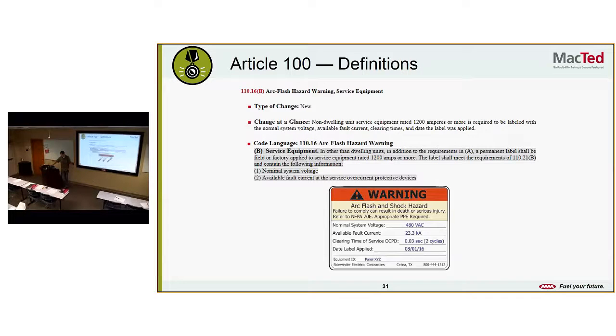Arc flash hazard warning. So this is another one of those labels like we were talking about where they're addressing that. You see this on panel boards, motor control centers, some larger air conditioning equipment. They'll go through and rate this as far as what type of arc flash you need, what the calorie content is as far as what the potential is, so you can calculate your arc flash needs. So this is for non-dwelling unit service equipment rated 1200 amps or more. It's required to be labeled with the normal system voltage, available fault current, clearing times, and date the label was applied. So that's non-dwelling, so no apartments, no houses, no condos, but industrial, commercial, that's where all that's going to apply.